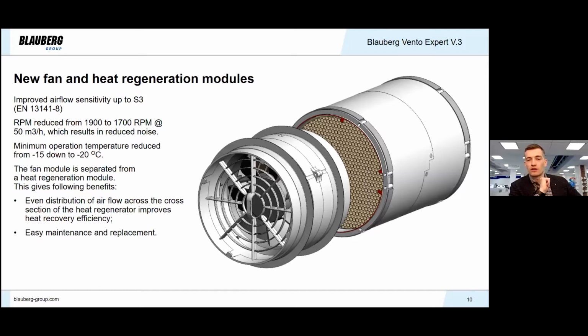Once again, the new fan and heat regeneration modules were developed specifically for this unit, the Blauberg Vento Expert. So we have improved, as I have already mentioned, airflow sensitivity up to S3 in comparison with the old cartridge. In the previous modification we didn't manage to get this good airflow sensitivity. RPMs were reduced from 1900 to 1700, still having 50 cubic meters per hour, and as a result we have reduced noise for the Vento unit.